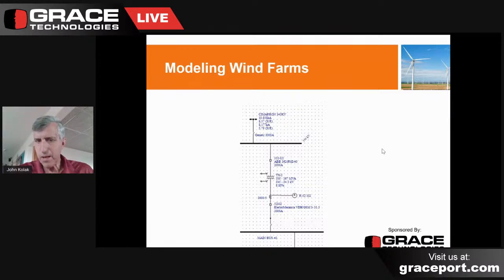We'll talk about how to model that in a second. But in a substation, we generally don't use time over current calculations as much as differential clearing, because in most cases on the sub, transformer, and bus, they usually are cleared by differential relays, and that will absolutely be the fastest clearing you're going to get in that situation.